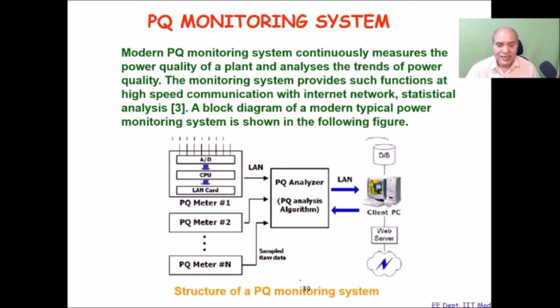Okay. This is a very general structure of a PQ monitoring system. You can see here there is a place where we put all the PQ meters. So they, basically 1 to n, measure all the important parameters, voltage and currents and so on. These are passed over to the PQ analyzer, where we analyze all these quantities, and then through LAN they are stored in the client PC. Okay, a data storage kind of a thing, which can be shared with the whole system, the client PC, and through a web server others can access this information to take decisions on the health of the power plant or any industry.